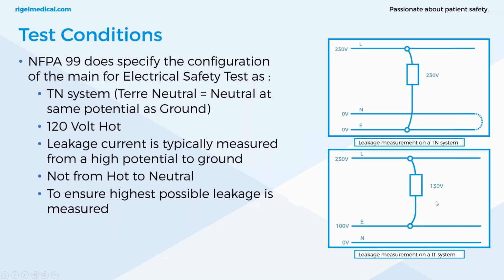Now, on an IT system, the highest potential from phase to earth is not achieved. So leakage currents are limited to the isolation levels of the supply. And no valid leakage limits or measurements can be taken because the safety analyzer is unable to produce an internal ground at half that line voltage.